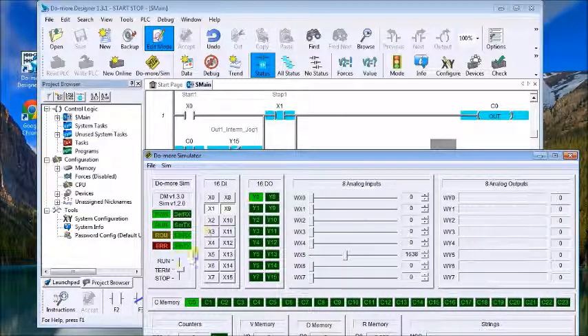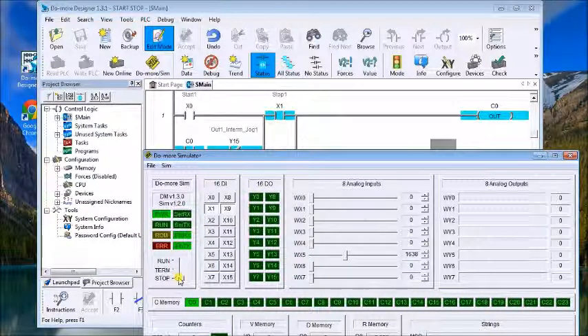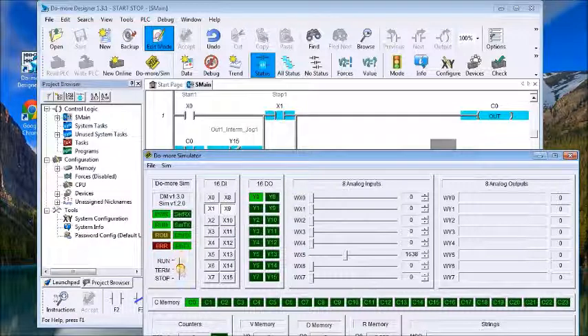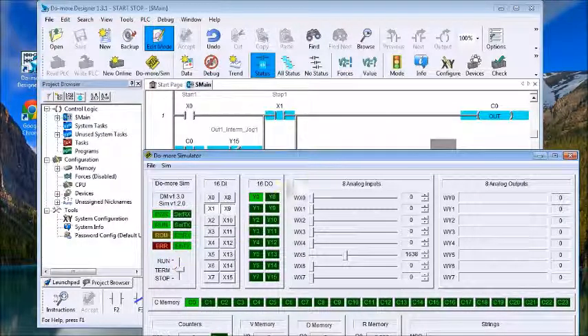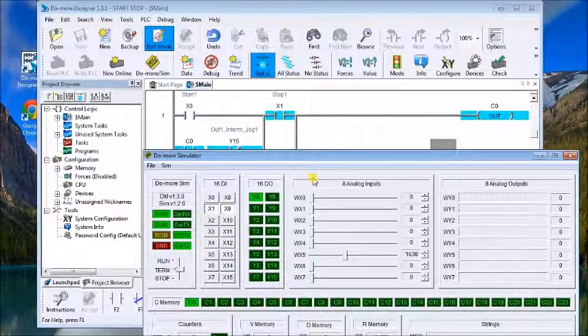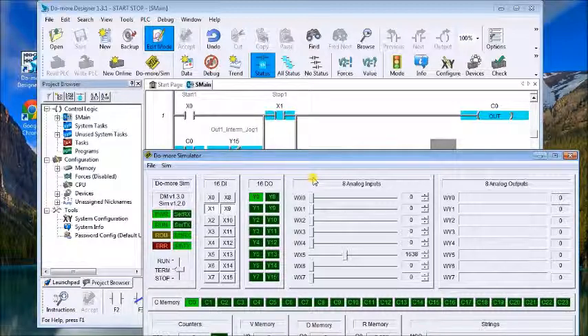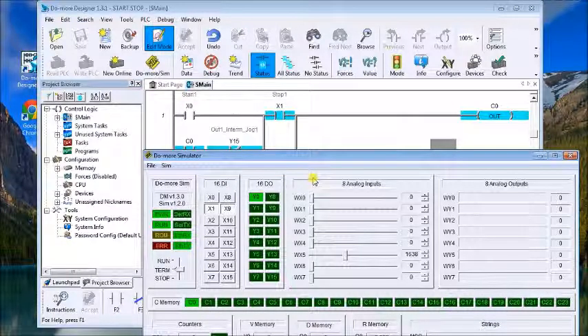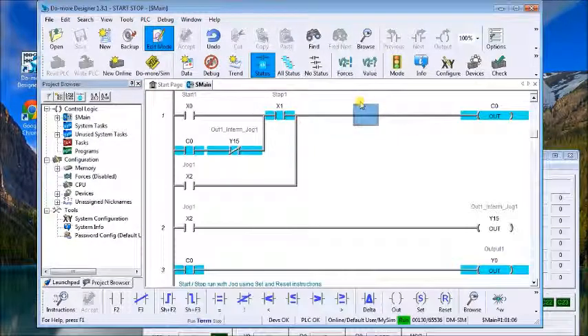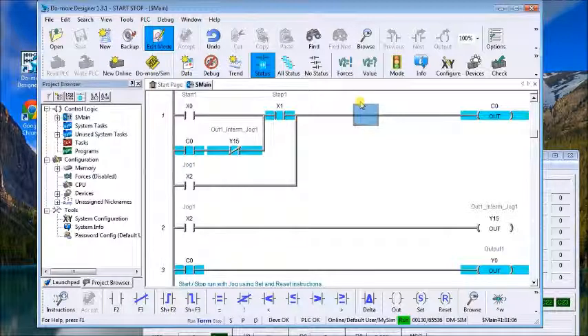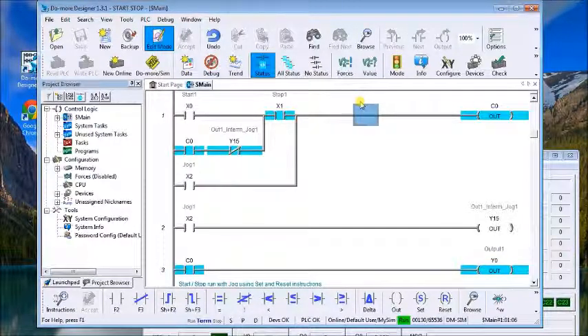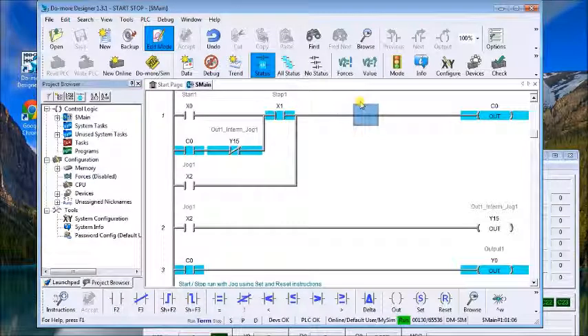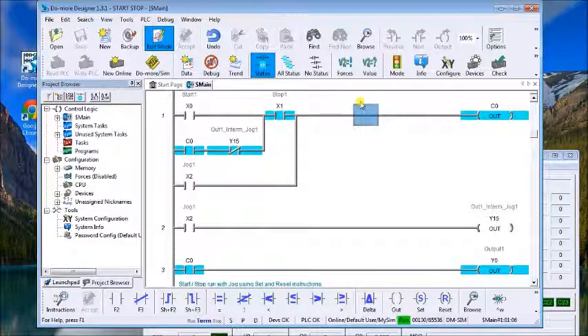Now if I turn off power and then turn it back on again, you'll see Y zero comes back on and remains the same way it was in the last state. So it's important when you write a program to ensure that all the outputs and inputs, when the power goes off, will come back into the state that you want them to.